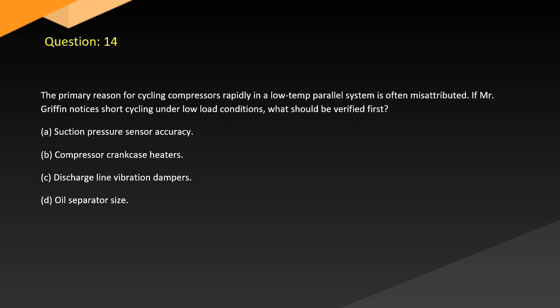Question 14. The primary reason for cycling compressors rapidly in a low-temp parallel system is often misattributed. If Mr. Griffin notices short cycling under low load conditions, what should be verified first? A. Suction pressure sensor accuracy. B. Compressor crankcase heaters. C. Discharge line vibration dampers. D. Oil separator size.